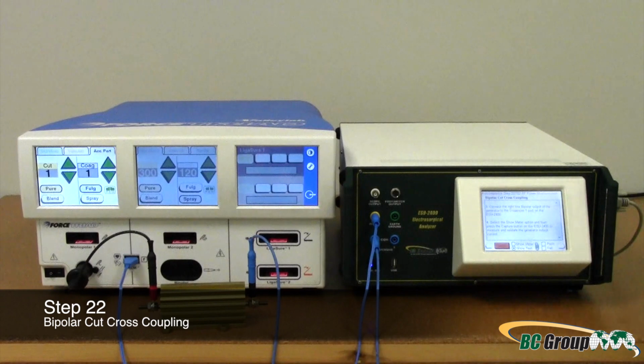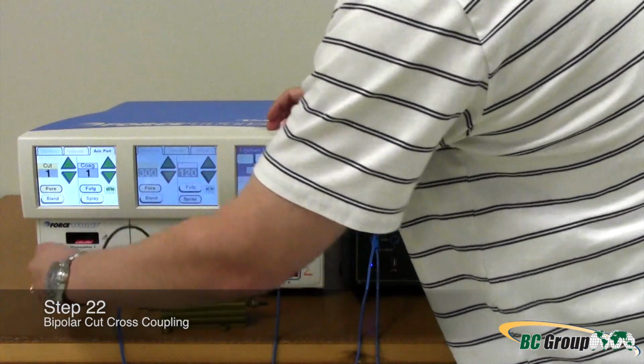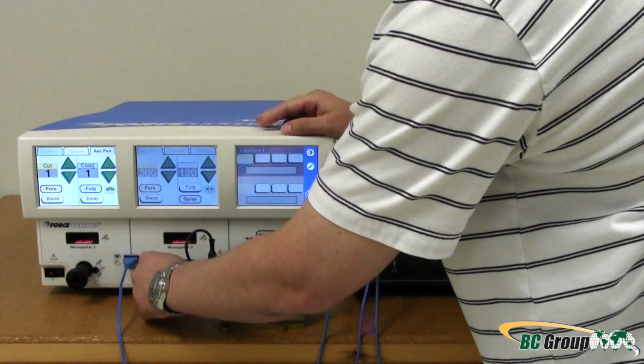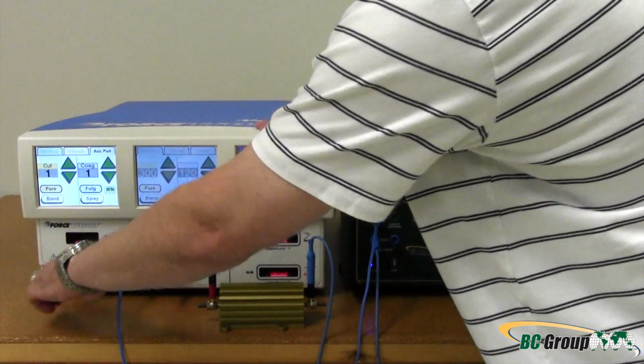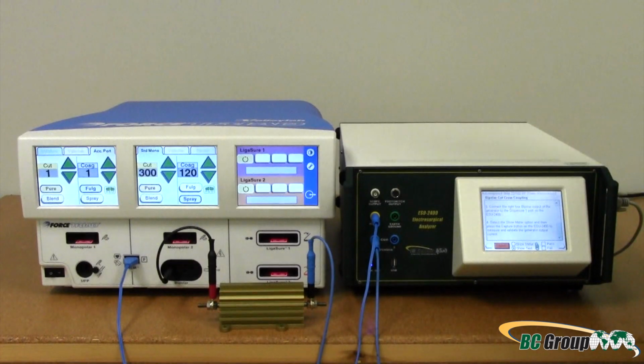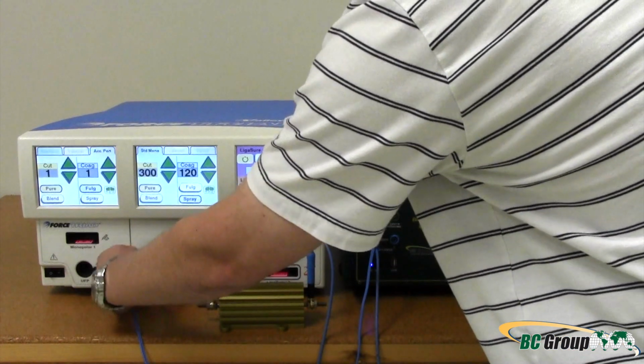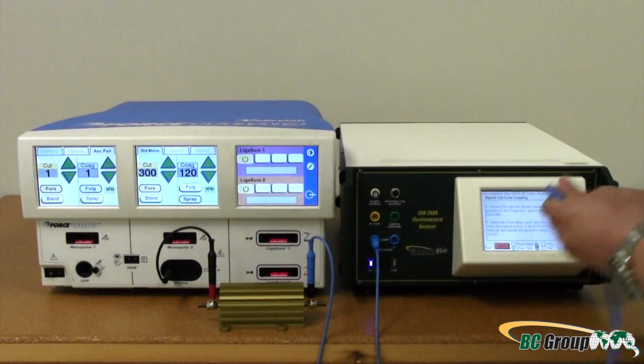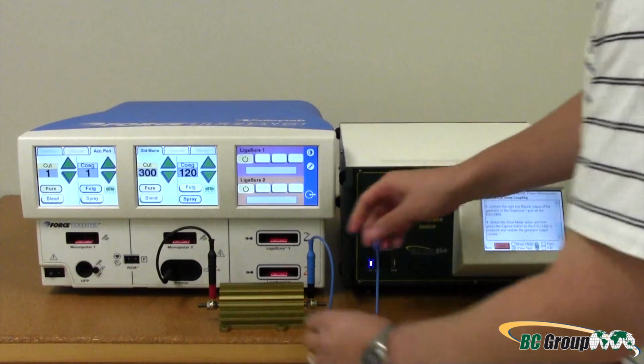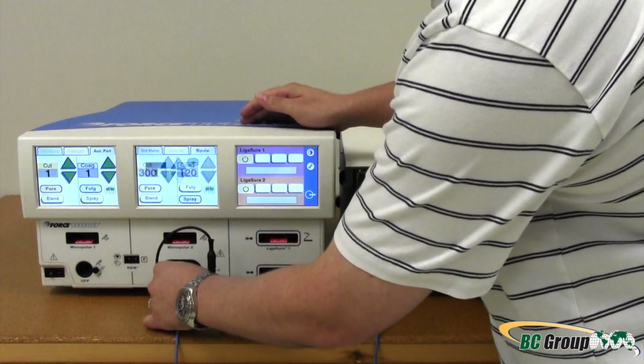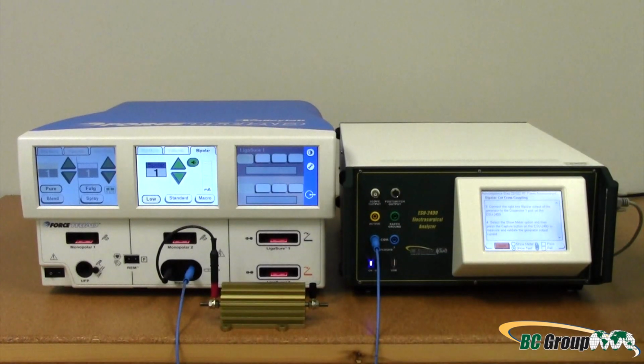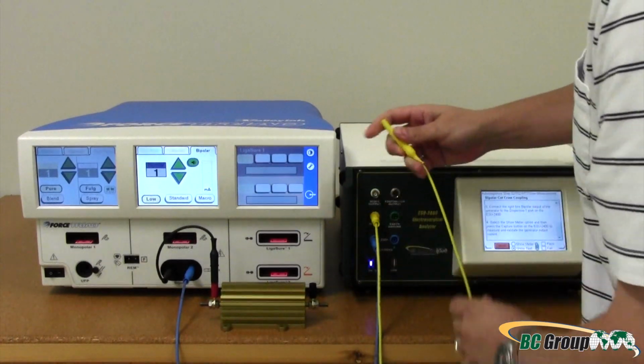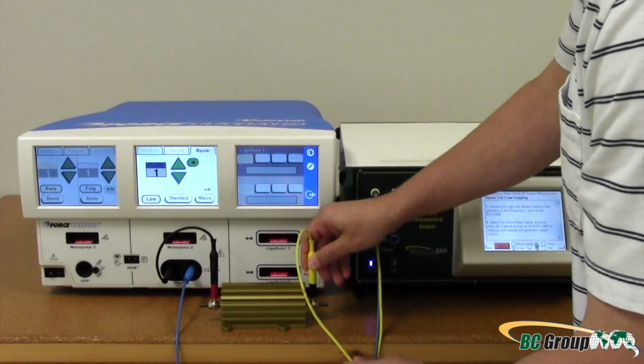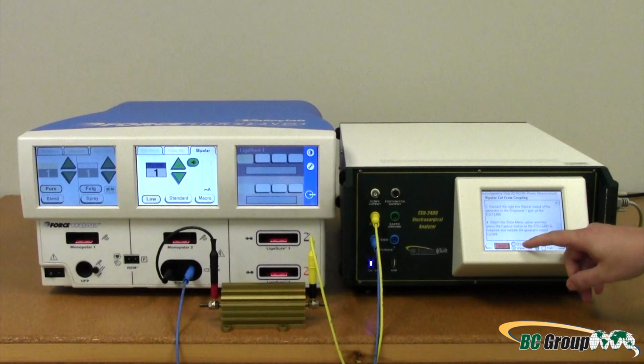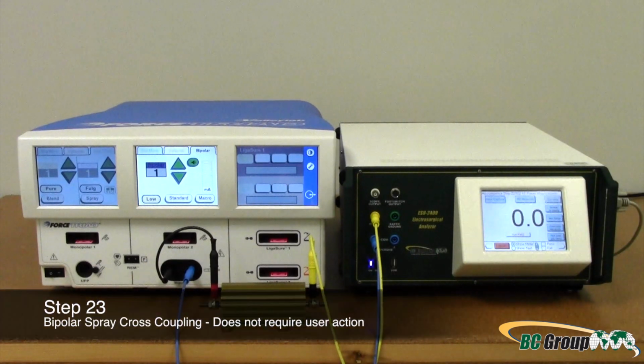Step 22. Bipolar cut, cross-coupling. Remove the short jumper lead from the UFP adapter and connect it to the left tine bipolar port. Remove the UFP adapter from the UFP port. Remove the cross-coupling lead. Connect the right tine of the bipolar port to the dispersive 1 port on the ESU-2400. Connect the ESU-2400 active lead to one end of the external load. Select Show Meter and then press Capture. Step 23 does not require user action.